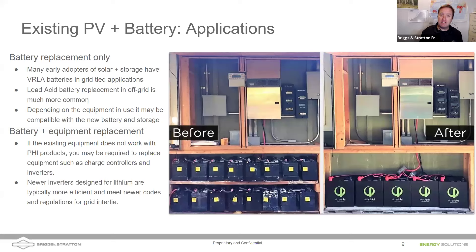What we want to do rather than replace them with new lead-acid batteries is have a conversation with the homeowner about replacing them with lithium-ion. It's going to cost more — replacing lead acid with a whole new lead acid set will be less than lithium-ion of any brand. But we want to help the homeowner look past that upfront price and look at the cost of having the batteries over their lifetime. These lithium-ion batteries might last twice as long, they don't need maintenance, and if the homeowner forgets to water them, there's no shortened life.